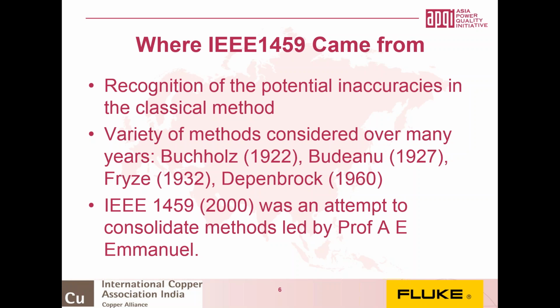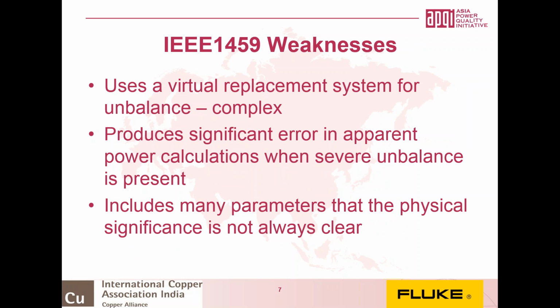So I've already mentioned that there are some problems with 1459. The first one, I would guess, for most people is that because it uses this virtual replacement system for unbalance, it has a certain level of complexity which creates a set of boundaries that are not always present in real installations. So you have to make some assumptions at the start that you are within the boundaries of the replacement system, but you may not be.